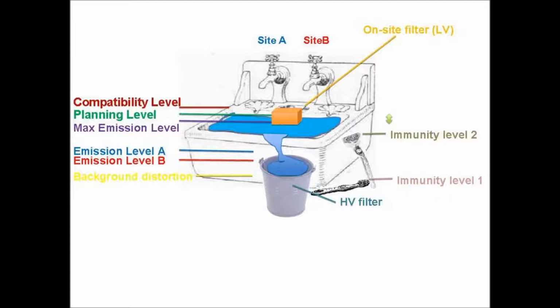The toothbrush is immunity level 1, which is, I don't know, some device that's connected onto the system. Could be your TV, could be your computer, could be anything. And then there's immunity level 2 for some other device. There are lots and lots of different devices, and they all have their own standards and their own immunity levels. But you really don't want to be messing with those levels. So in such a case, where you're going to have an overflow from your node onto the system at large, you're going to need a filter. And in this case, you need a bucket. So that's basically what we've been trying to do in the last while, looking at various filters to minimise the impact on your toothbrush or your razor or whatever else it happens to be on the system.